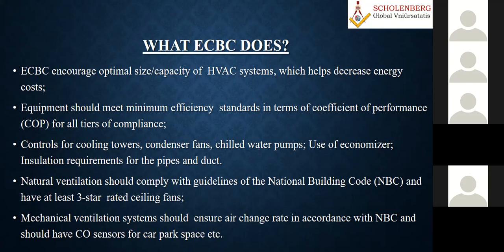Now, similarly, if you are going for natural ventilation, it should also comply with the guidelines. Some of the buildings here, one of the hospitals here, was designed by a UK consultant maybe 40 years ago. In a room inside, they put a split air conditioner, floor mounted in those days, not even ceiling mounted. But there is no fan. The advantage of a fan is forced air convection. Many times you need not run the air conditioners, because maybe in the month of November or December, if there is a fan for air circulation, and you just open the small windows, that will give some ventilation. You don't need to run air conditioners. But unfortunately, here it is not like that. You have to run them all the time, otherwise you will have suffocation.